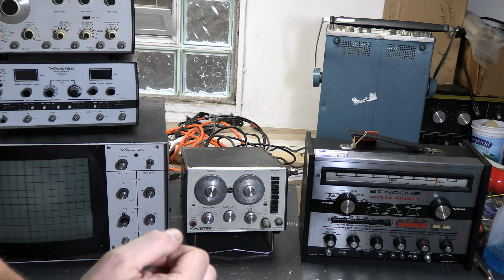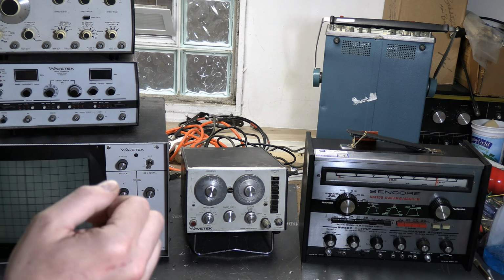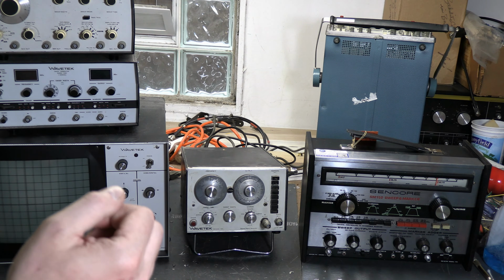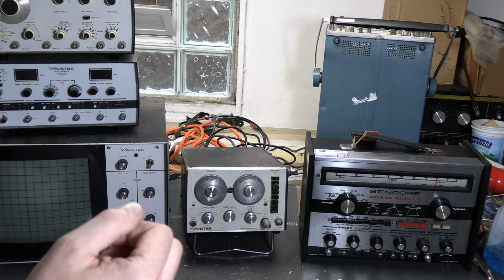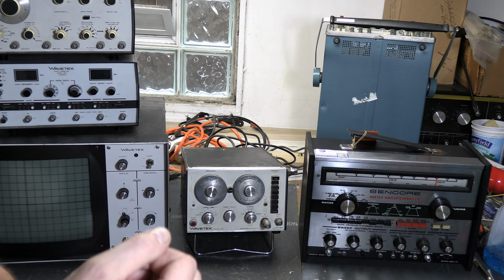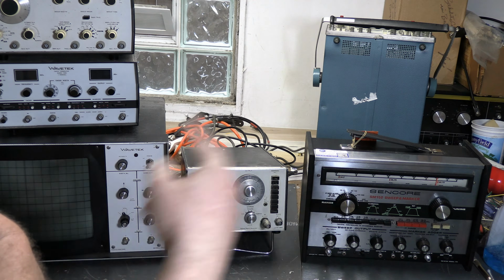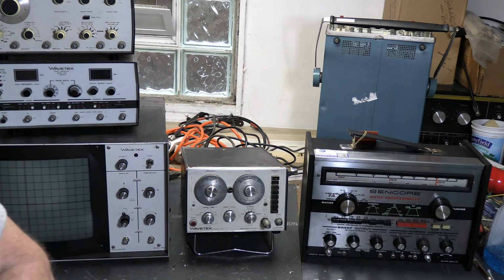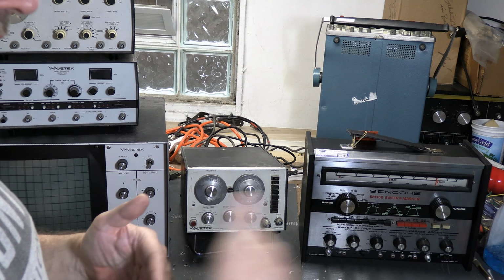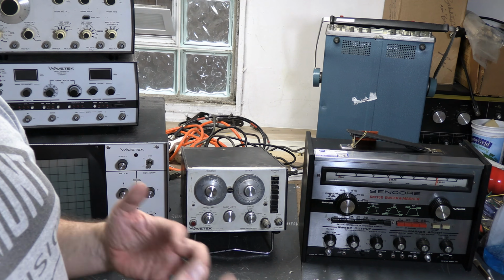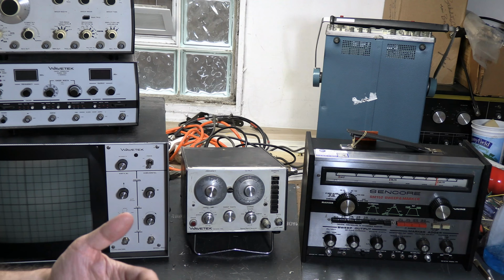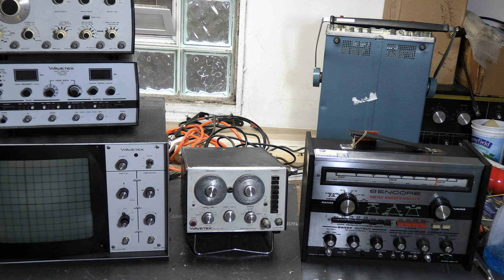They will require TLC. You're going to have to calibrate them. You're going to have to live with some limitations. For example, the sweep repetition rate on these old sweep gens, typically they just use the AC line. It's just a 60 hertz sine wave, and they're driving the sweep generator with that, which sometimes you want a slower sweep rate, because how quickly you're going between the frequencies can affect how the display looks.